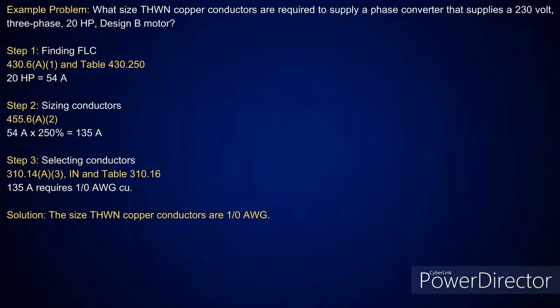And this in here, this deals with phase conversion. Now, what you're going to see is a little variance here from what we usually see. But this is where you're protecting the phase conversion on the conductors and everything. And they're going to tell you that the conductors have to be protected. In this case, you're still going to look at Table 430.250 to get the amperage rating for the motor. In this case, we have a three-phase 20 horsepower motor. It's good for 54 amps. But if you go look at 455.6(A)(2), it's going to tell you that it has to be taken at 250% for the conductors.